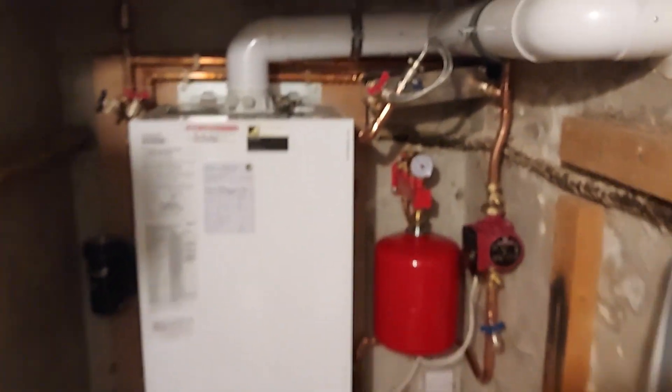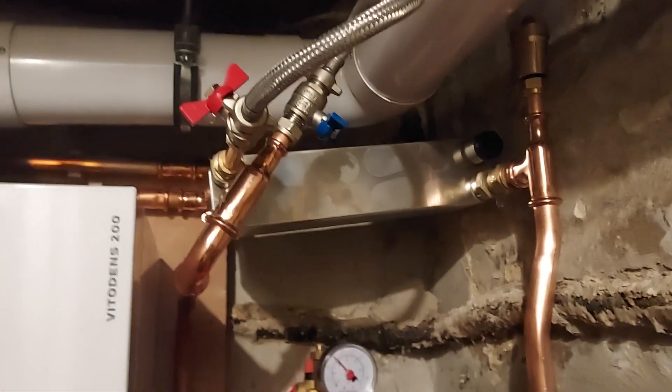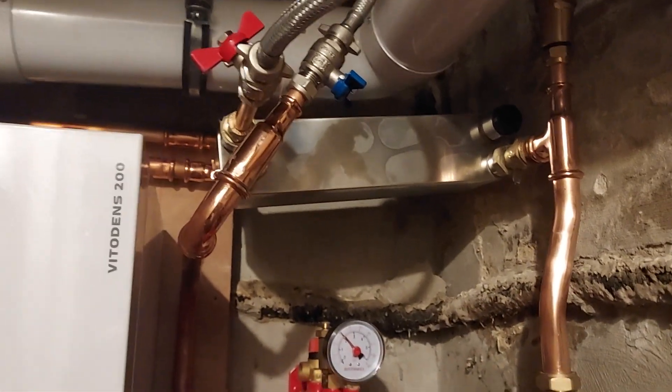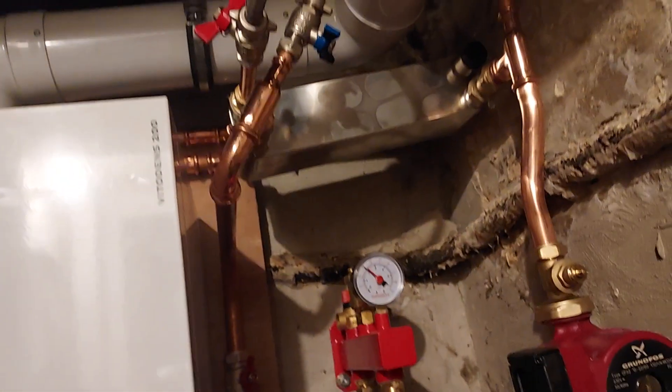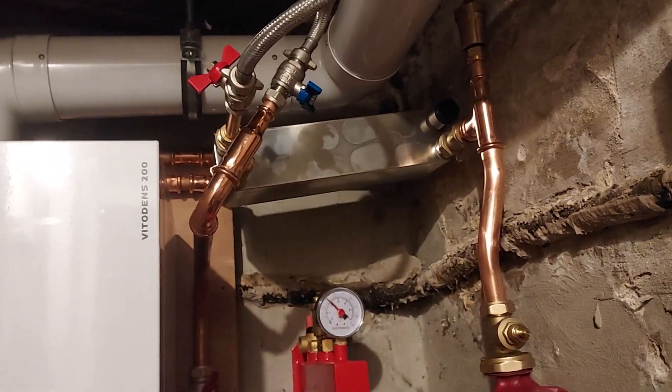A little more plate separation — forgive the light — we've got a little plate heat exchanger up there. So this system is suffering from scale. This is one of the newer ones which has got almost no rubber in it, by the way, and it doesn't matter if they've got rubber or not, they still scale.